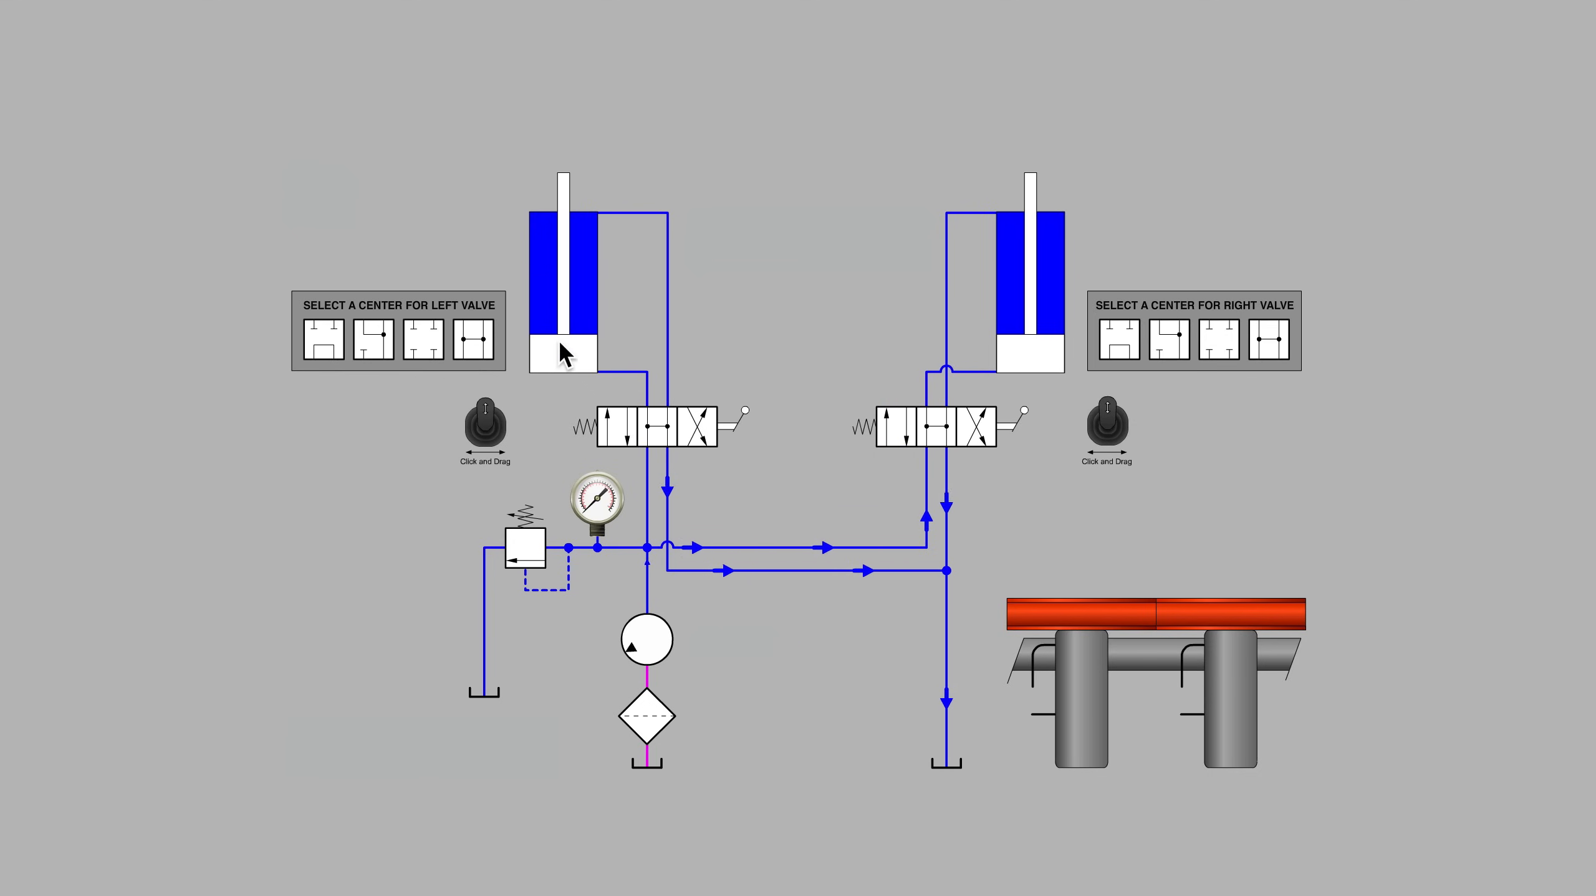In addition to needing to be able to position each cylinder individually to the correct position as we would like, an additional criteria is that we would like to avoid pumping fluid over the relief valve for prolonged periods of time while the cylinders are in their hold position and we're going to be leaving the pump running. So a pair of open center valves do not work. We've already established that.